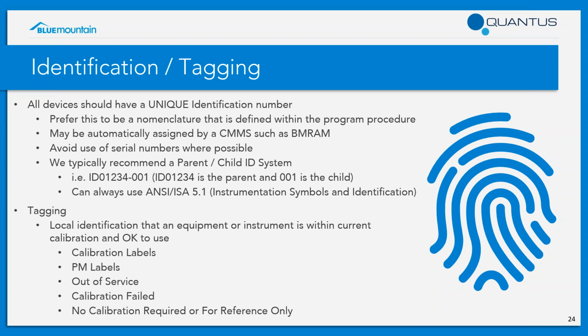We do get a lot of questions about that last one, or when or what should I sticker with no calibration required? Some customers have a ton of instrumentation all throughout their facility with their HVAC systems that don't require calibration. The thought of identifying all those is paralyzing, because there could be thousands of instruments that we're not testing. So what we typically recommend is to take the visible equipment in your GMP areas that doesn't require calibration. Those are the ones you should really focus on. They should have an equipment master record to document the decision that no calibration is required. It should be identified, and then it should be labeled with a no calibration required sticker. That will really help you from focusing on all the instruments in your program and narrow it down to what's important.